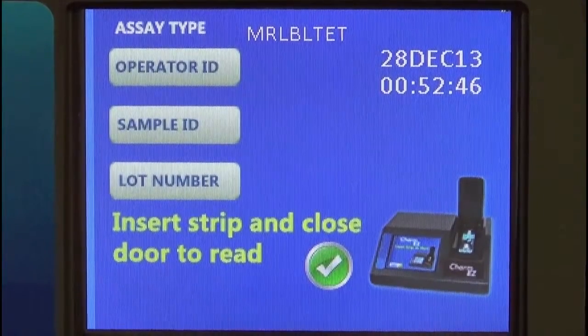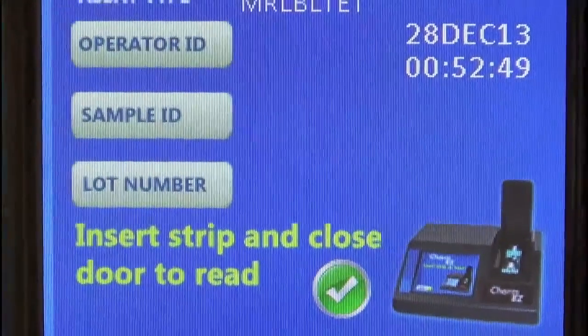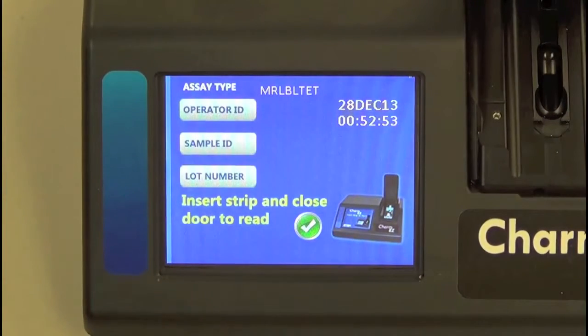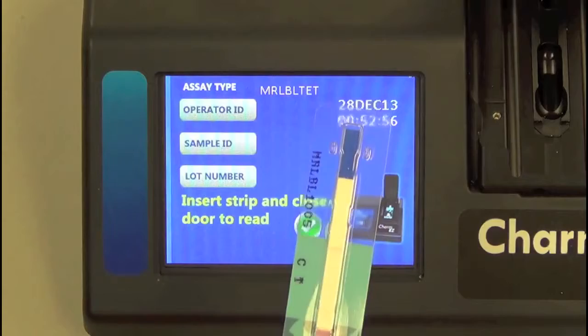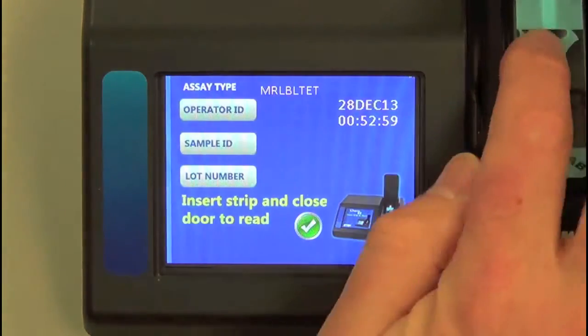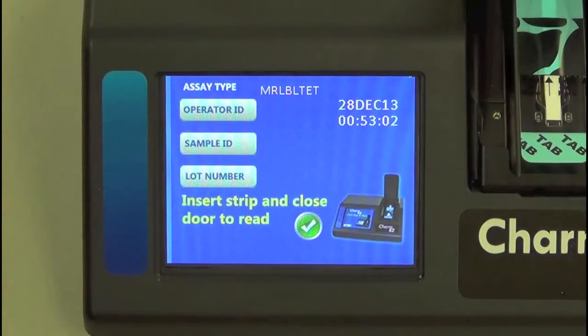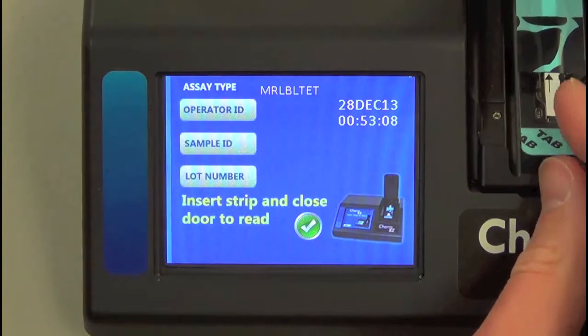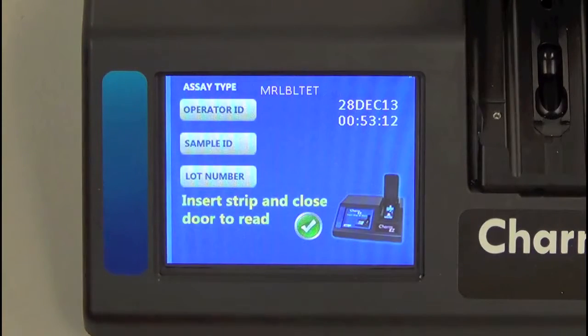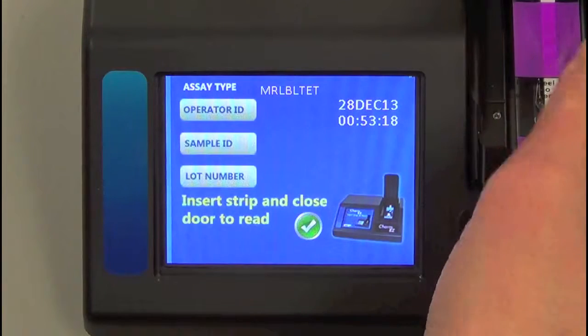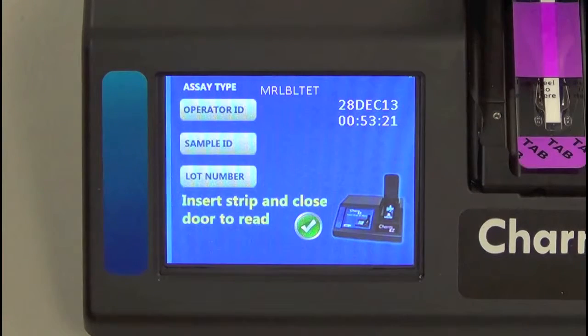And if we pan out here for a minute, what we're going to do is show you that if we put in a blue strip, which is your MRL-BL1, it is going to load and it's going to still remain on that screen for MRL-BL TET. So the color sensor does not detect the blue color and it does not change the channel calibration. If we remove this and we add the light blue, which is your MRL-AFMQ test, again, the color sensor in this force test mode is inactivated and will not load the proper calibration values. So you're in essence forcing the reader to interpret every strip that's put into it as that MRL-BL TET test.